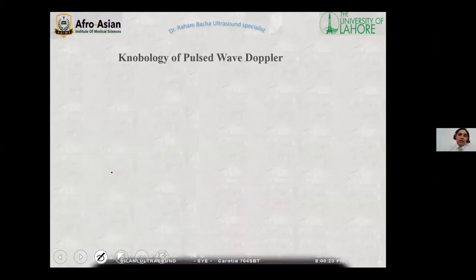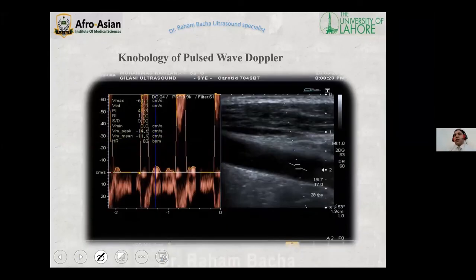And one thing which we have to discuss is spectral Doppler aliasing. Whenever there is aliasing in the spectral Doppler, it is utmost important to correct it. You can correct spectral Doppler aliasing, first of all, by adjusting the baseline. If there is still aliasing in spite of adjusting the baseline, then you will have to increase the scale by increasing the PRF. If again there is aliasing, then you will have to decrease the Doppler frequency. If still there is aliasing, then you will have to increase the angle.